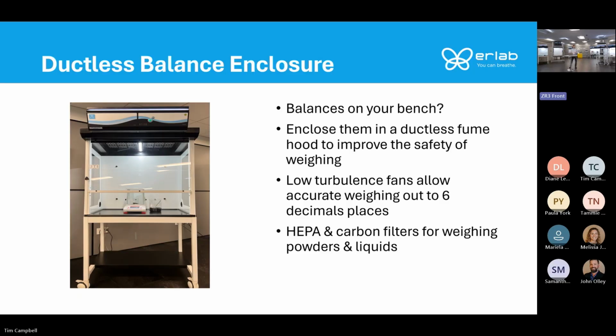Typically, we hear from people after the fact, after they've had an exposure incident. Maybe they were weighing a hazardous powder and the researcher was exposed, or you're weighing liquid chemicals as well. Those chemical vapors are going past your breathing zone. Putting a balance in a ductless fume hood, which is very low turbulence, completely encloses the procedure, isolates the worker from the hazard, and will significantly improve the safety of weighing. Ductless fume hoods are very low turbulence, so you can actually weigh out to 6 decimal places. By having that flexible filtration column, you can have both HEPA and carbon filtration, so you can weigh both powders and liquids in the enclosure.